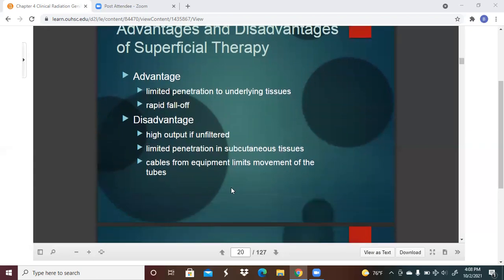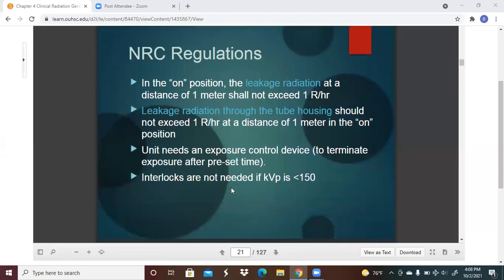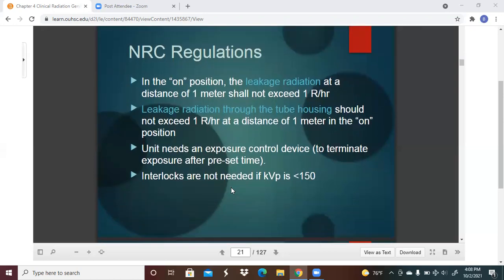So what are some NRC regulations regarding these devices? Well, in the on position, the leakage radiation at a distance of 1 meter should not exceed 1 roentgen per hour. The leakage radiation through the tube housing should not exceed 1 roentgen per hour at a distance of 1 meter in the on position.